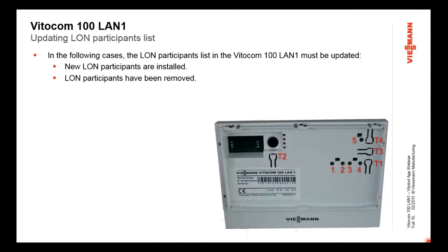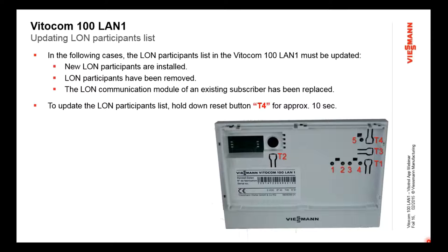But this is just so that all of the addresses are refreshed and new, so that we don't miss anybody, we don't have any duplications, that kind of thing. So again, every LON module has a subscriber number. So if you replace the card in a unit, you also then have to do a LON participant check because its new card will have a different subscriber number. And you simply do that participant check by holding the T4 button. You see the T4 button over here. And the T4 button then, if you hold it for 10 seconds, will do a LON participant check.